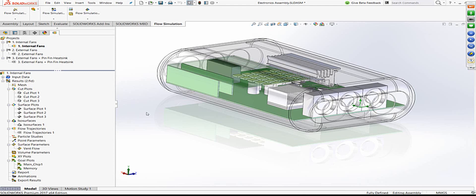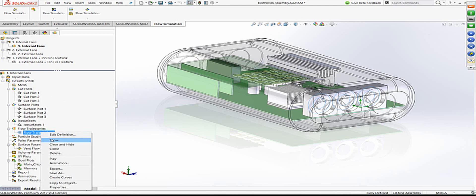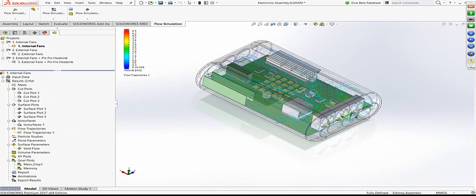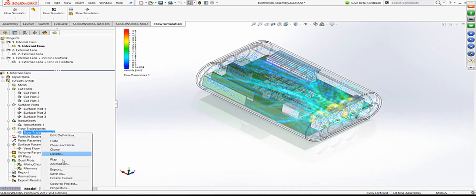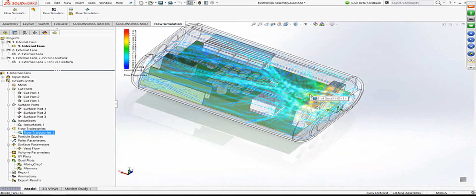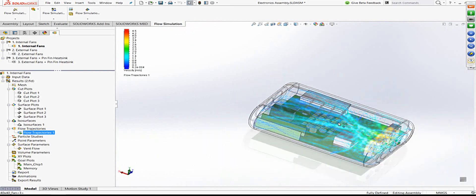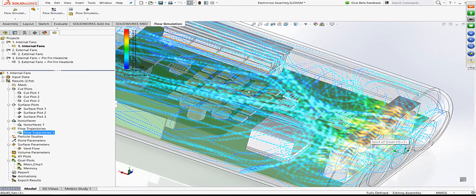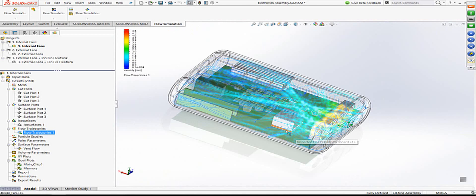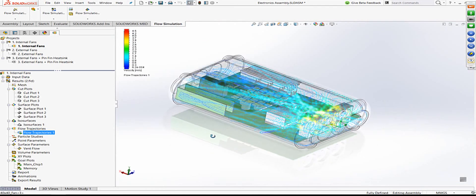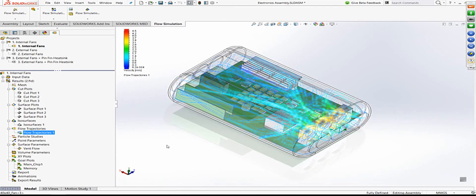Now let's look at the results, starting with flow trajectories, which show how air moves inside the system. An internal fan is pushing air inside. Certain air exits, and some is recirculating. Most importantly, air takes heat from the chip through the heat sink and carries it out of the system. This is one of the key results to observe.